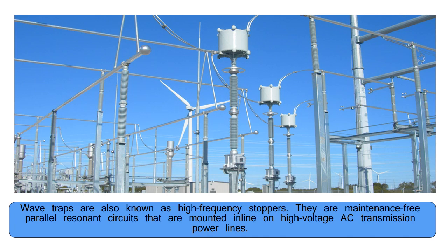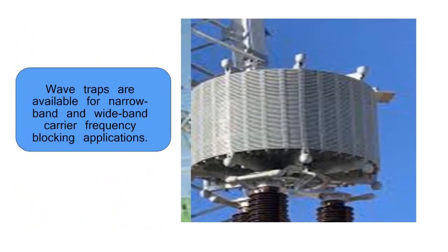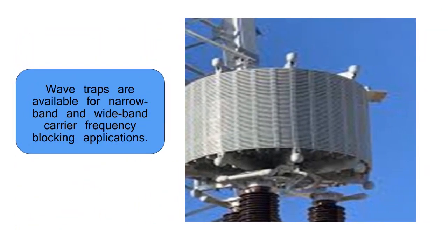They are maintenance-free parallel resonant circuits that are mounted inline on high-voltage AC transmission power lines. They are designed to carry the rated power frequency current and to withstand substation fault currents. Wave traps are available for narrowband and wideband carrier frequency blocking applications.